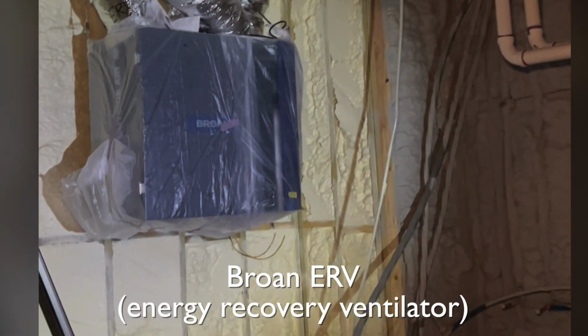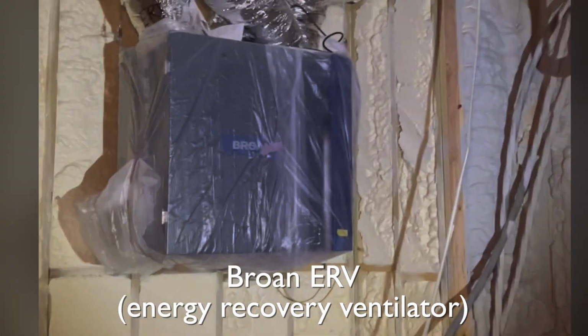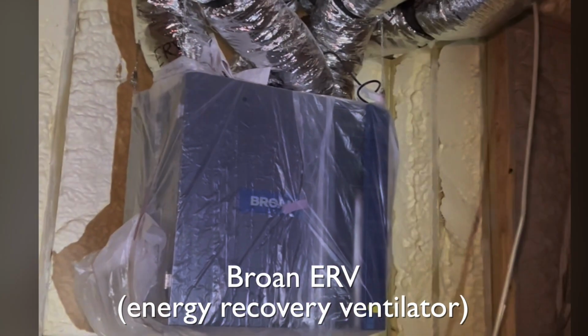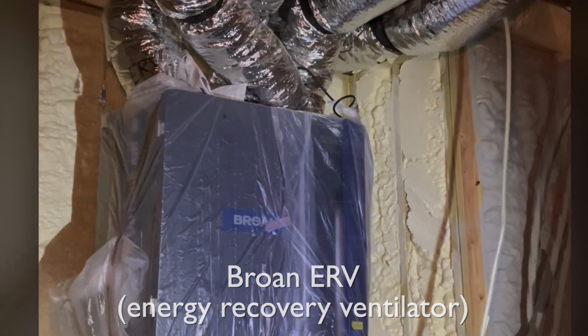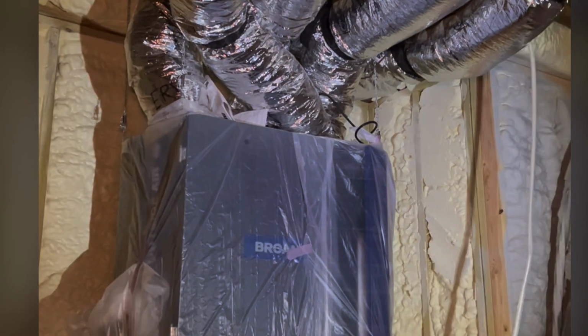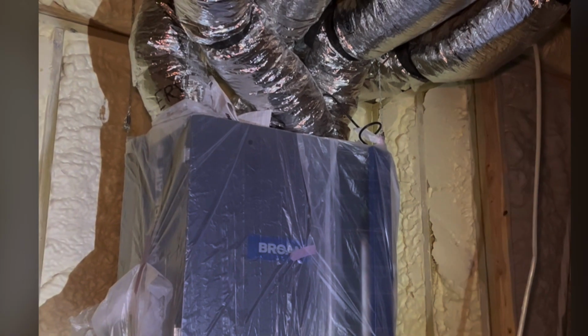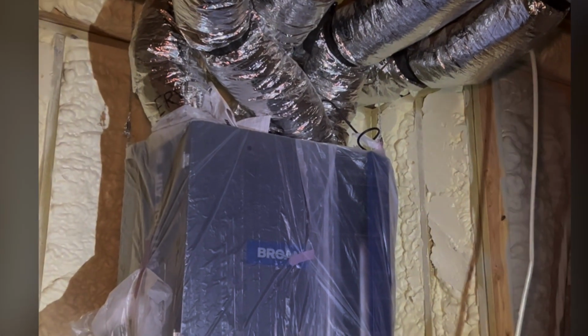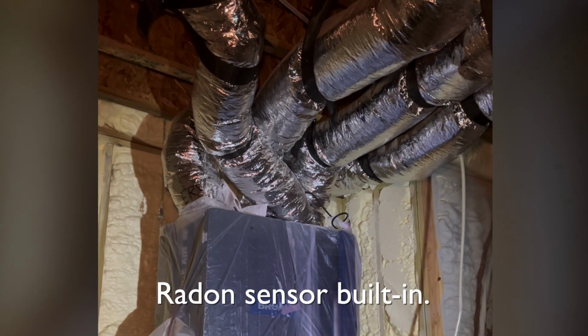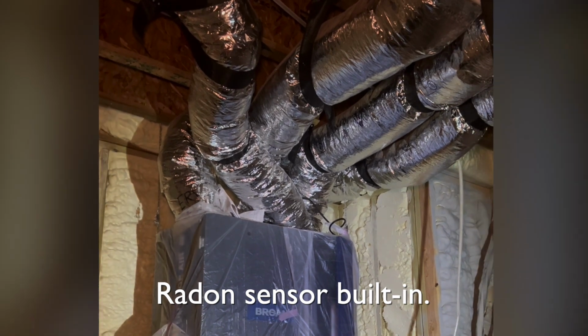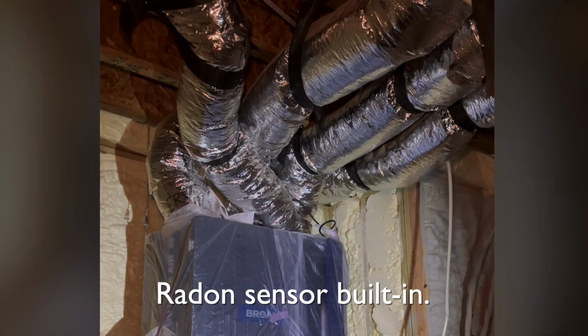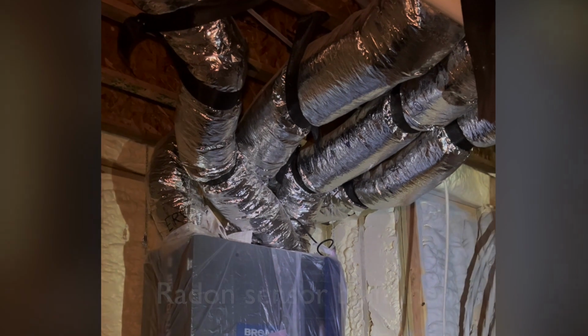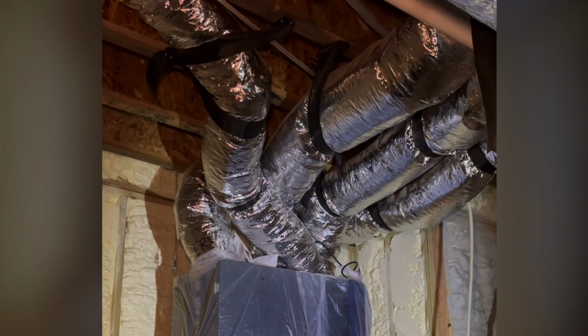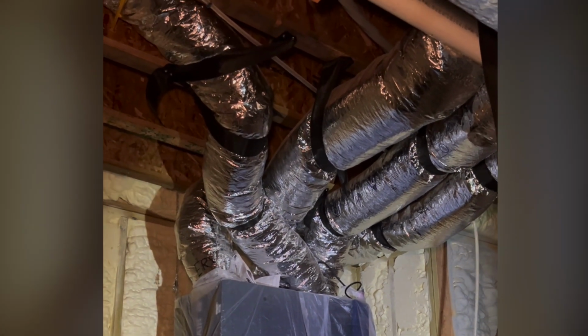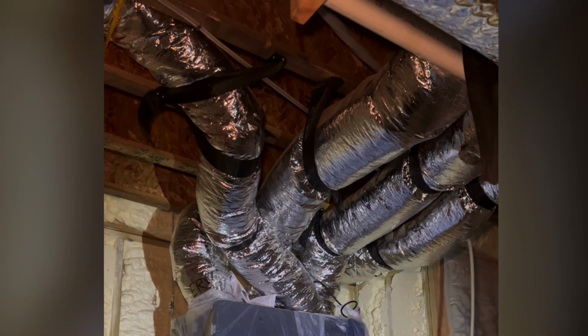To the left, we have a really exciting ERV. This has the ability to control the amount of fresh air you bring in. We'll properly program that. And then we've added a sensor permanently installed in the basement bedroom area that will monitor radon. And if radon levels go above 4, it will actually increase the fresh air intake to help dilute that radon. So these are really cool, savvy ways of ensuring you have basic fresh air, indoor air quality needs, as well as kind of handling the unknowns of radon mitigation as well.